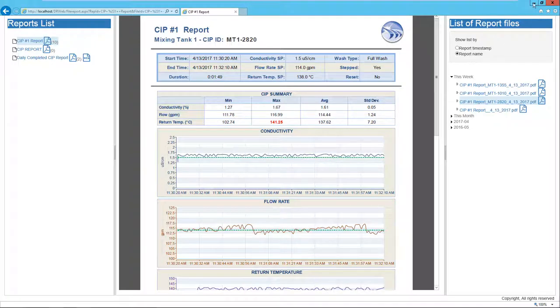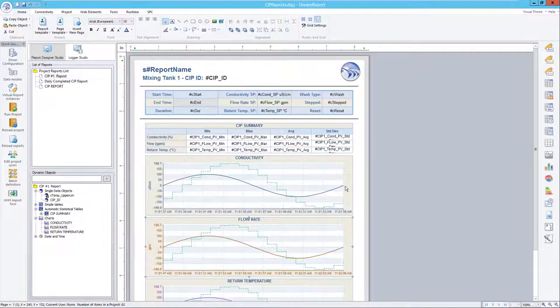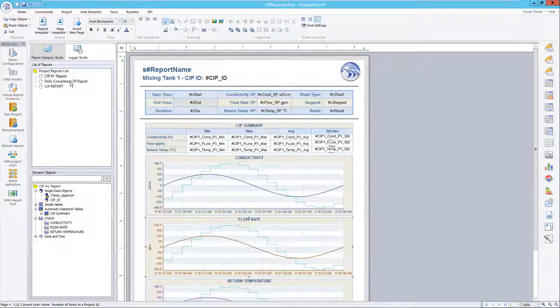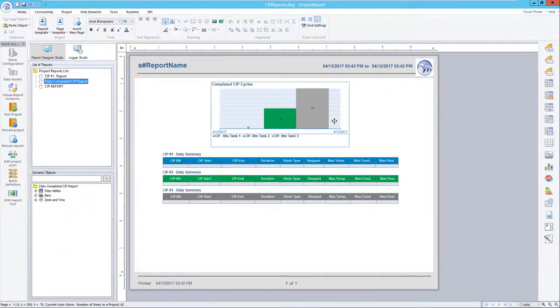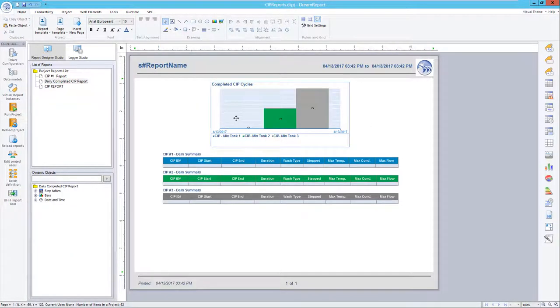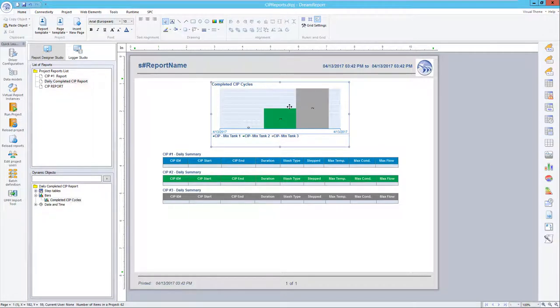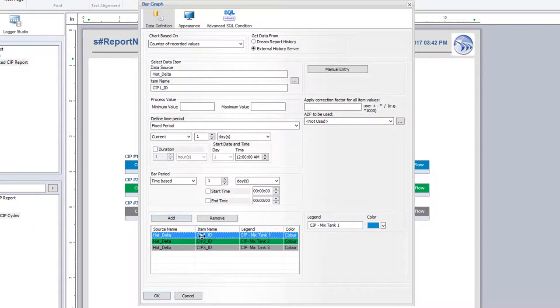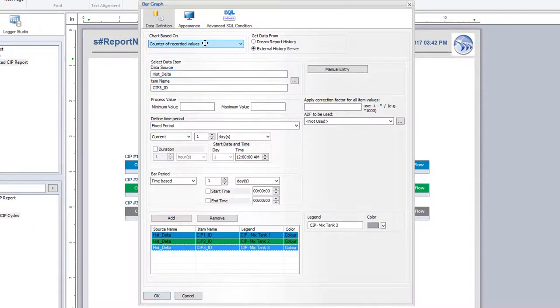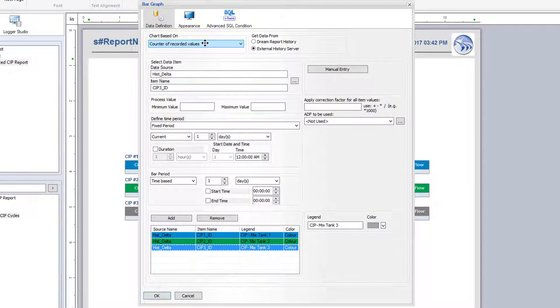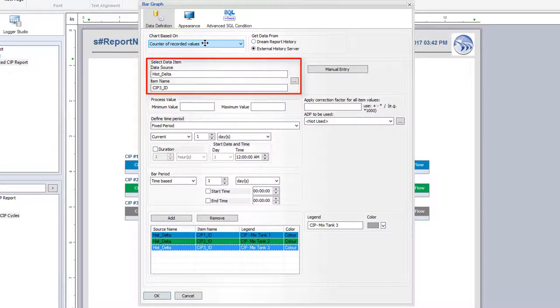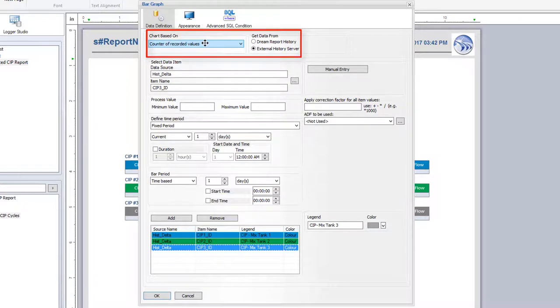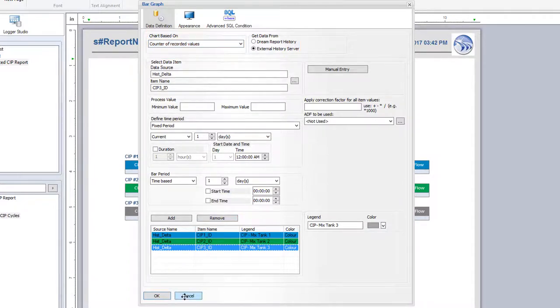The other interesting thing we can do is not just run the raw CIP reports, but maybe create a report that shows all CIPs run on a daily or a weekly basis, by mixing tank, with key statistics shown for each CIP ID. Here on this report, I've used a bar graph to graphically show how many CIPs were run on each tank. This was done by looking at the CIP IDs for each tank, and using DreamReport's built-in counter of logged values to come up with my bar values.